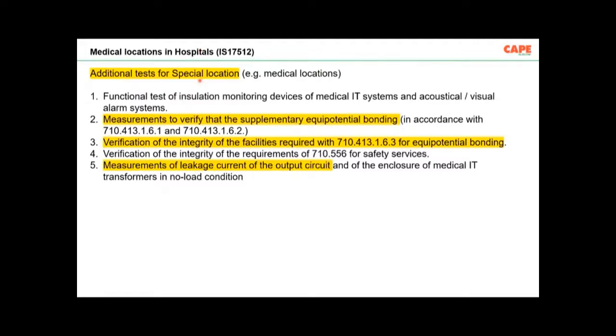Special location is, for example, an operation theater, or an ICU, or the locations where class 1, class 2 medical equipments are used. The class 1, class 2 medical locations are there. So for those cases, number 2, measurement to verify that supplementary equipotential bonding. What is supplementary equipotential bonding?